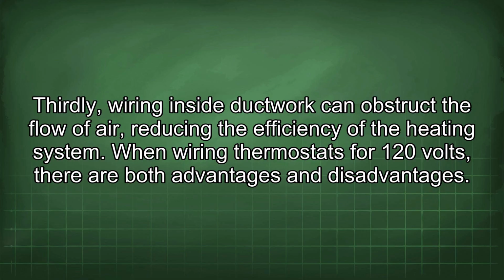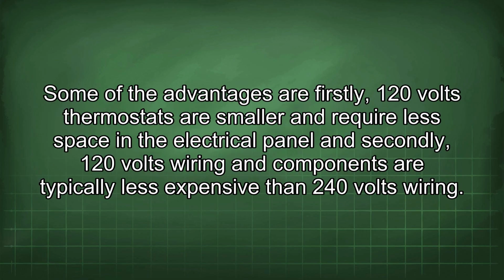When wiring thermostats for 120 volts, there are both advantages and disadvantages. Some of the advantages are: firstly, 120 volt thermostats are smaller and require less space in the electrical panel, and secondly, 120 volt wiring and components are typically less expensive than 240 volt wiring.